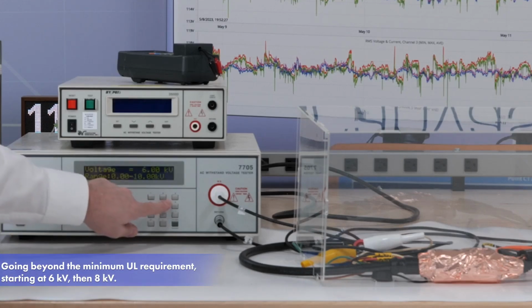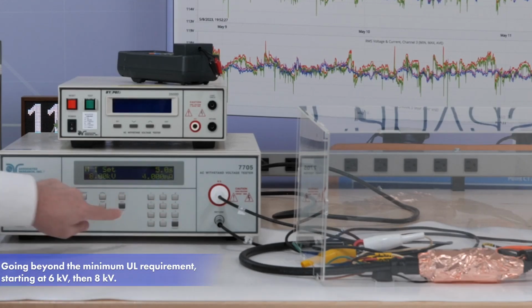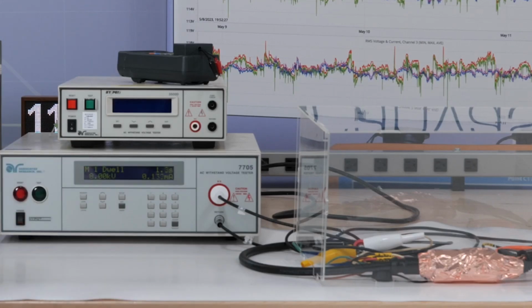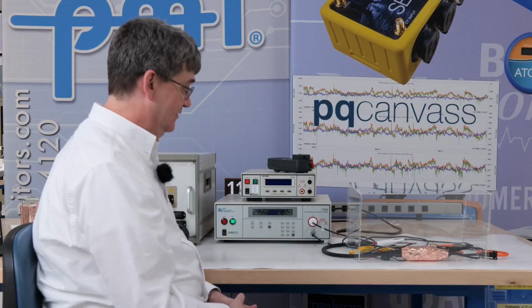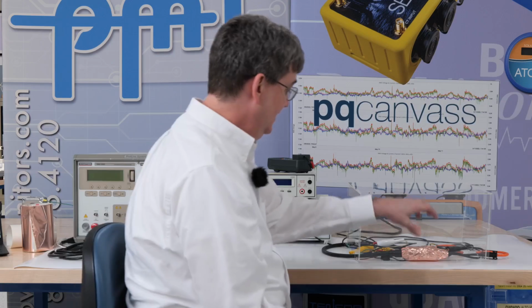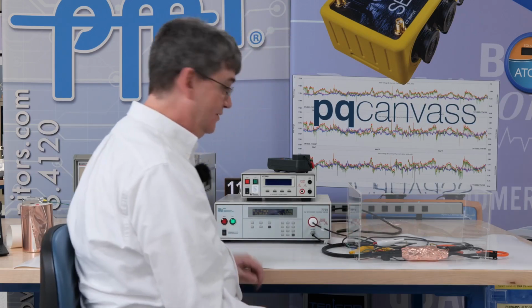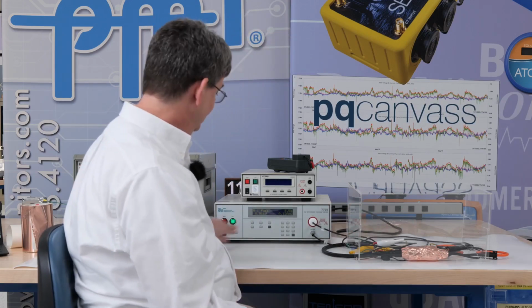Now we're going to go all the way to 8 kV to make sure we have a lot of margin in this for the safety test. And we also pass at 8 kV. Now let's try this in a different configuration. You may be holding the CTs or the voltage connector. So we're going to move the copper foil to a different position.